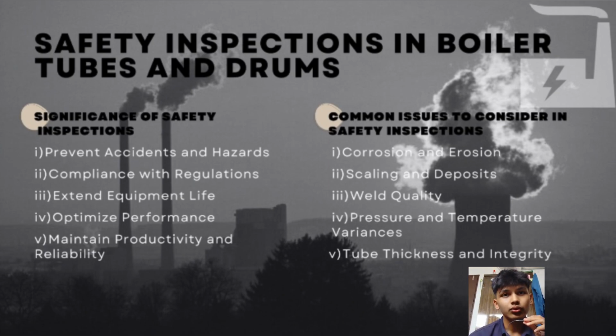The first common issue to consider in safety inspections is corrosion and erosion. Boiler tubes and drums are susceptible to corrosion and erosion, which can weaken the structure and lead to failures. Inspections should focus on identifying signs of corrosion and erosion and assessing their severity. Next is scaling and deposits. Accumulation of scale and deposits on boiler surfaces can reduce efficiency and obstruct heat transfer. Inspections should assess the extent of scaling and determine the appropriate cleaning and maintenance procedures.